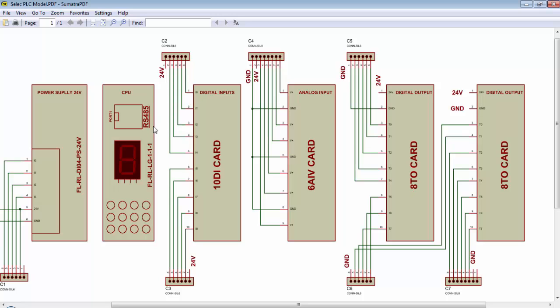The RS485 communication port is required to connect the PLC to a computer to transfer the logic into PLC. Remember that the power supply required for this PLC is 24V DC. The PLC's digital inputs will accept 24V signal for high and 0V signal for a low.